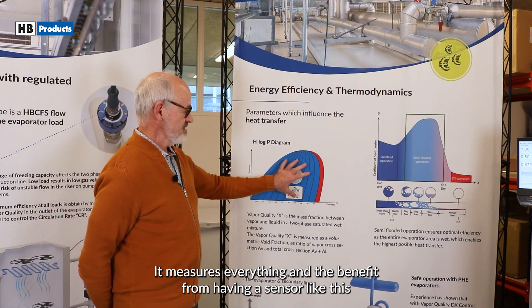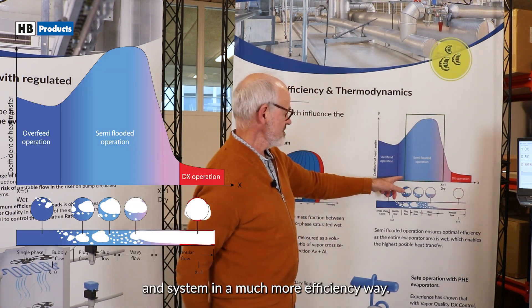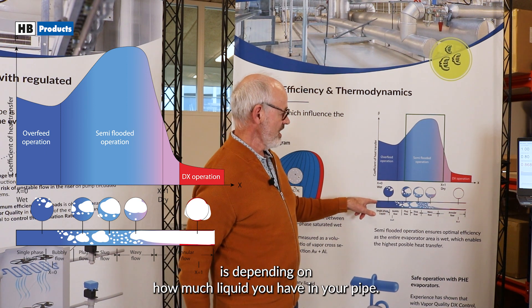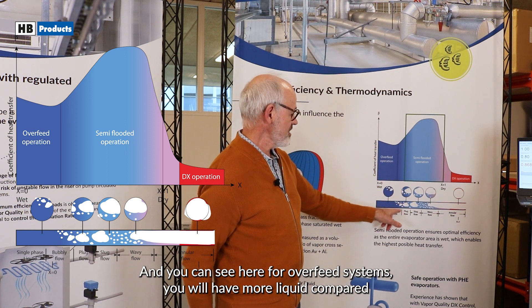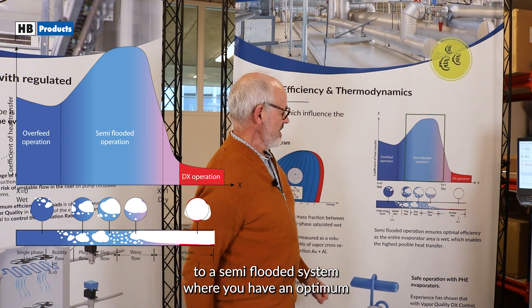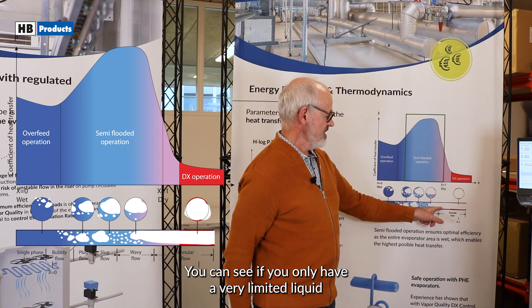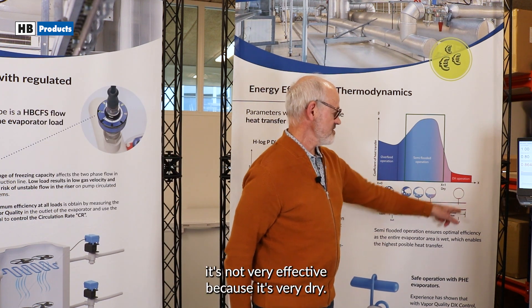And the benefit from having a sensor like this is that you are able to control your evaporator and system in a much more efficient way. The heat transfer coefficient is very dependent on how much liquid you have in your pipe. And you can see here, for overfeed systems, you will have more liquid compared to a semi-flooded system, where you have an optimum mixture of liquid and vapor. For example, with superheat, if you only have very limited liquid in your evaporator tubes, it's not very efficient because it's very dry.